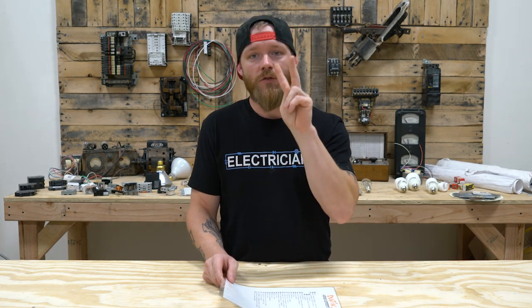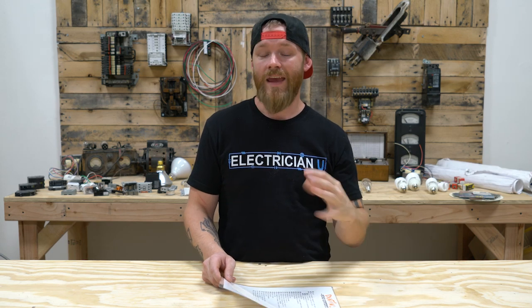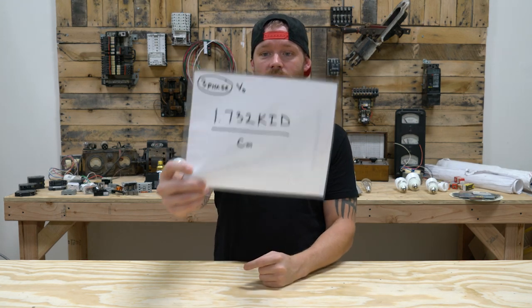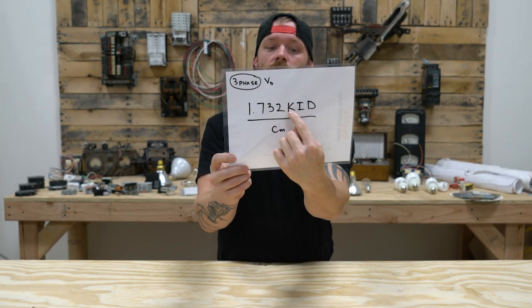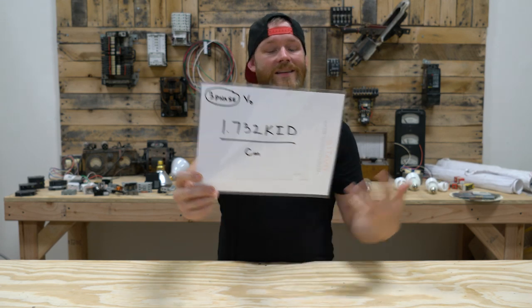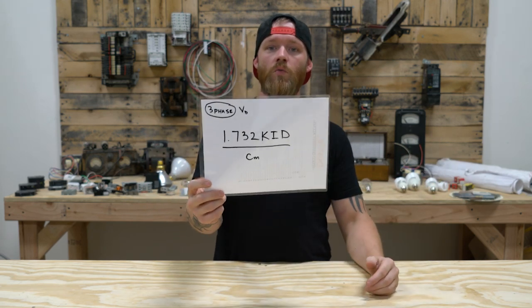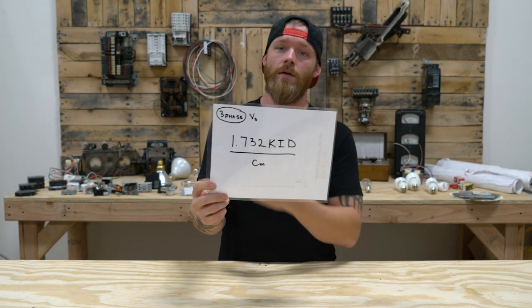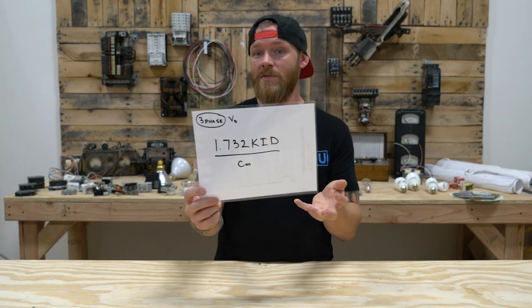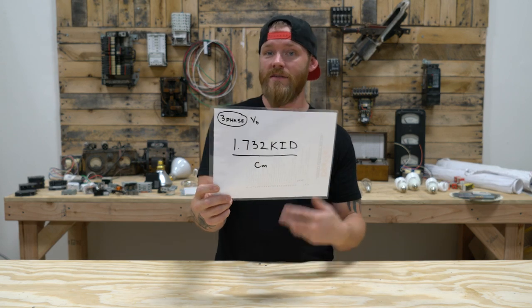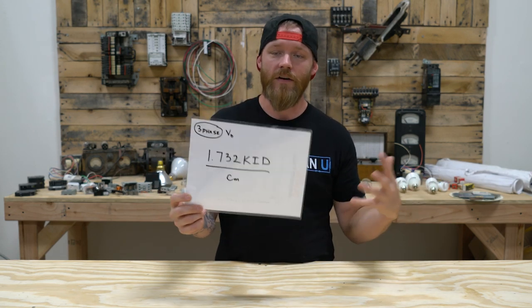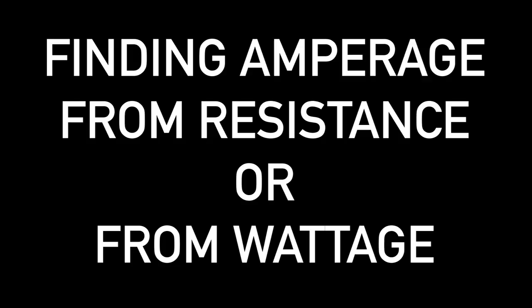One quick thing to mention about that is that the examples I just showed are for two conductors for a 120 volt circuit. So that's a little bit different than a three phase. You can't use anything I just talked about for three phase. For three phase, you actually have to use this: 1.732 times K times I times D over the circular mils. You have to do that because the normal Ohm's law wheel that I was just showing you doesn't figure in the fact that you have three hots. Typically, voltage drop is going to be slightly less on a three-phase circuit for the same amperage, but I just figured I'd throw that little tidbit in there.